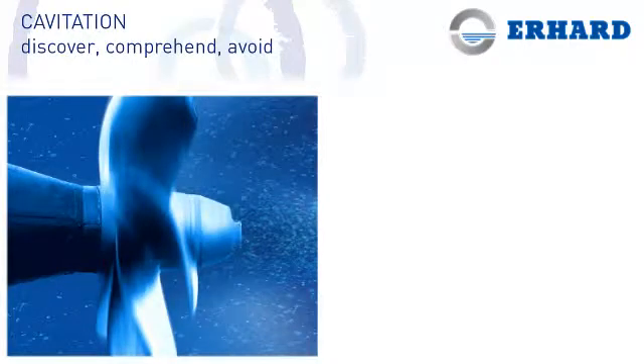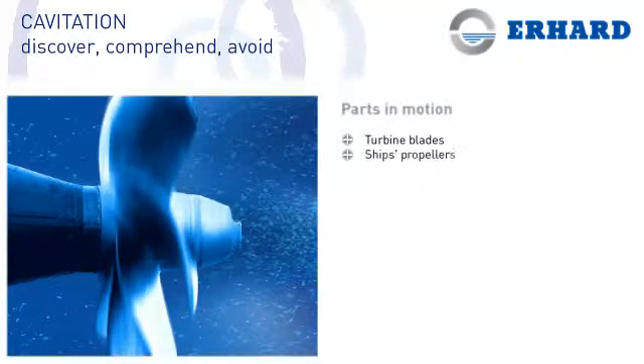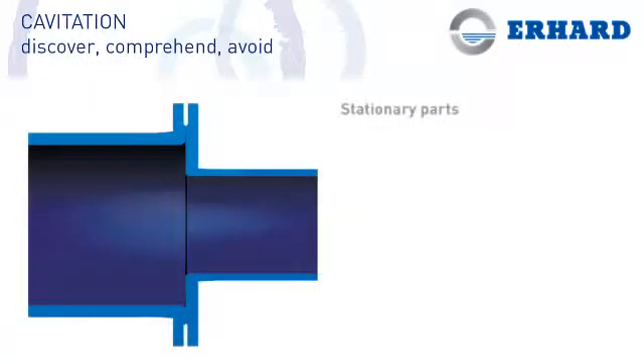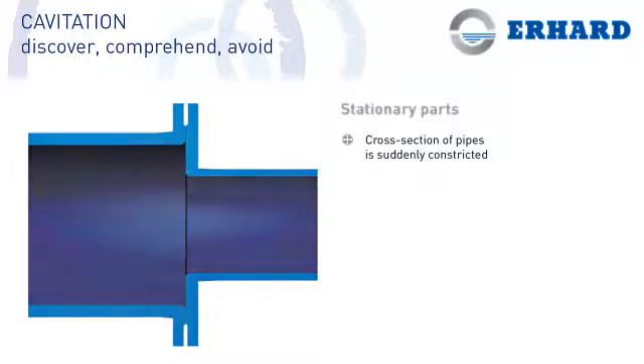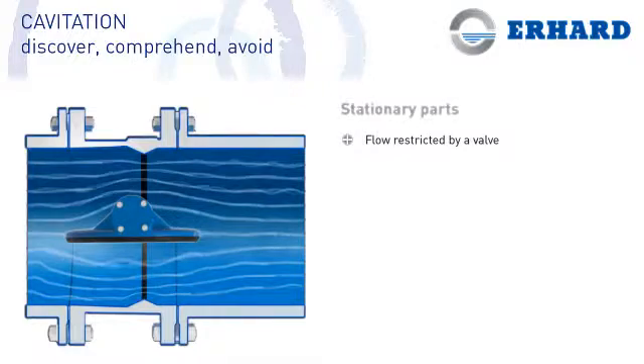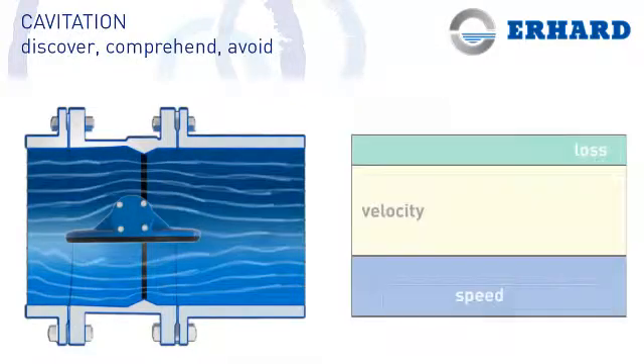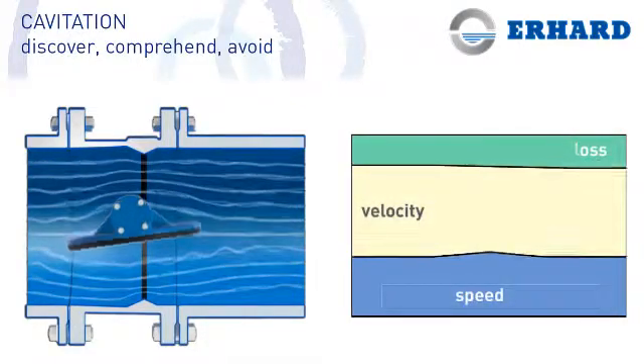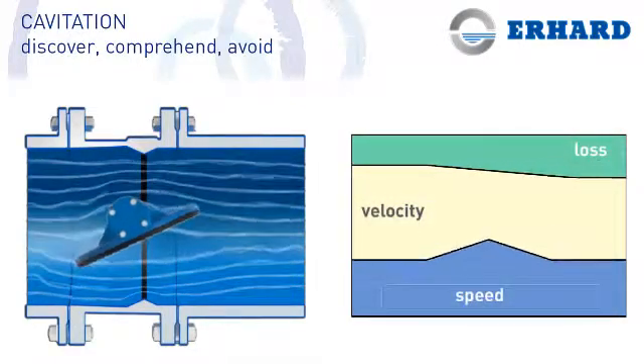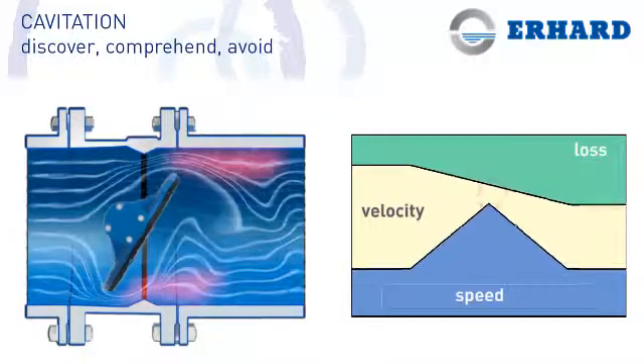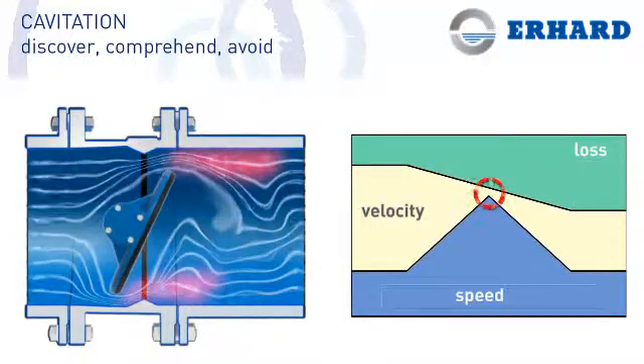Cavitation, for example, can occur in turbine blades or ship's propellers, but stationary parts are also affected by it — for example, if the cross-section of pipes is suddenly constricted, or if the flow is restricted by a valve. Strong velocity conversions are generally the cause of the pressure changes which initiate cavitation.